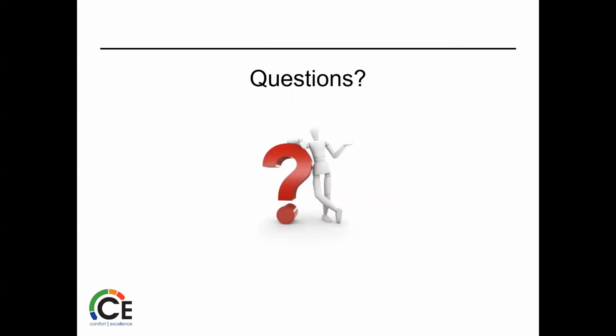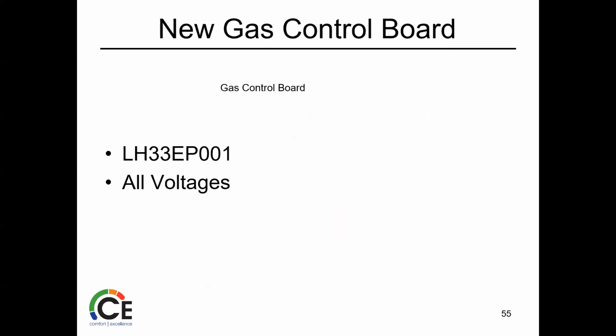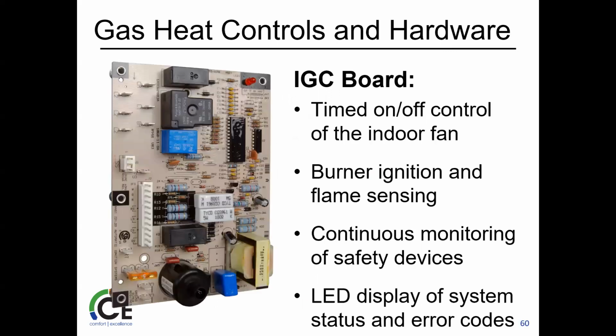All right. Questions? Pretty simple stuff. Talk about the IGC board now. Now that part number has changed, and I apologize, I didn't have time to change it, but the board stayed the same. So this is your ignition control board, timed off control for the indoor fan. So again, once we're talking heating, it takes care of the fan. It's going to do that delay, let that heat exchanger heat up a little bit so we don't get much of a cold blow. Burner ignition, flame sensing, all done through the board.